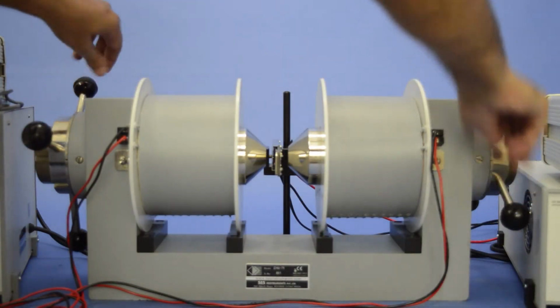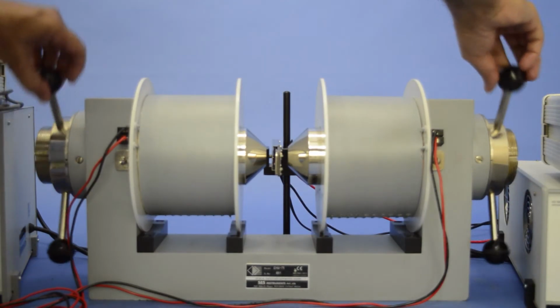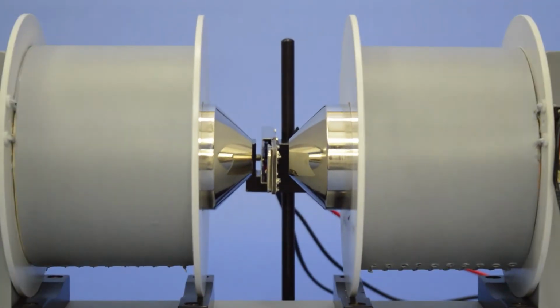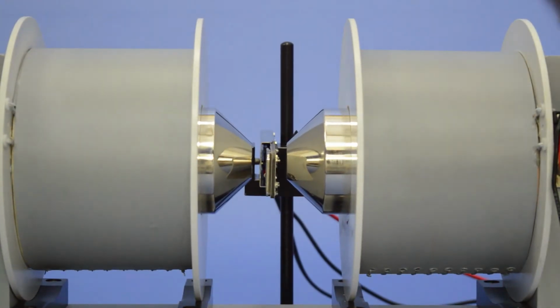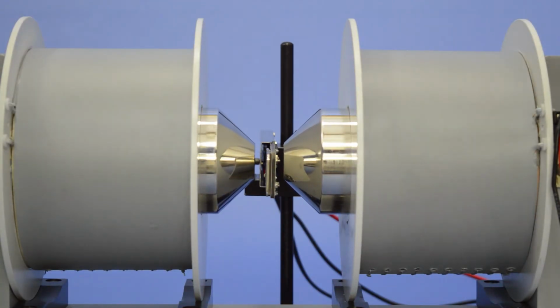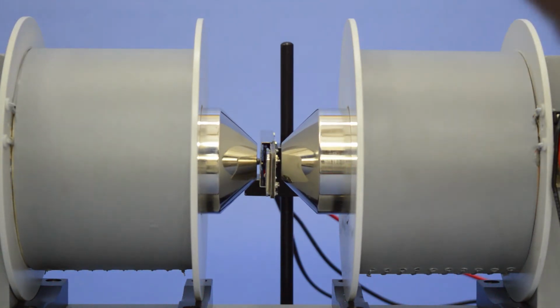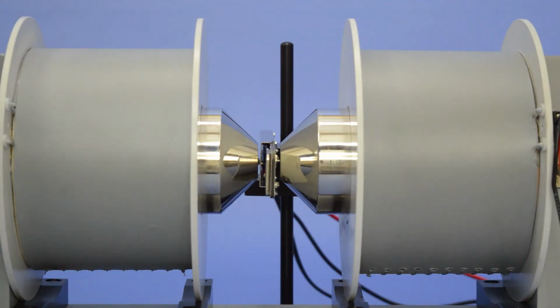Set the air gap between the pole pieces of the magnet by placing the silver or tungsten probes at the center of the magnet. The pole gap should be set as narrow as possible.